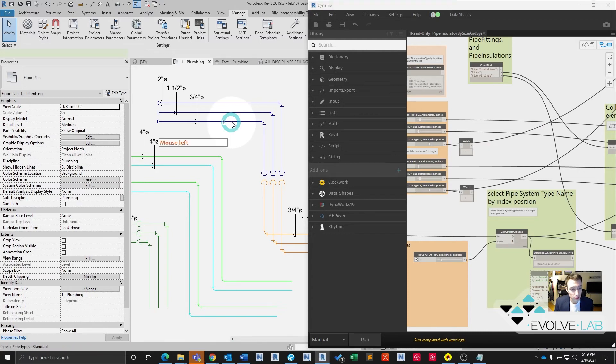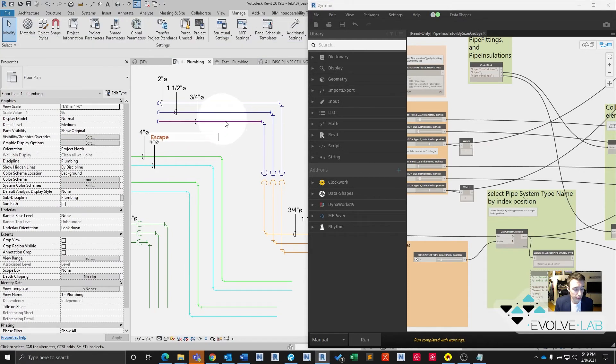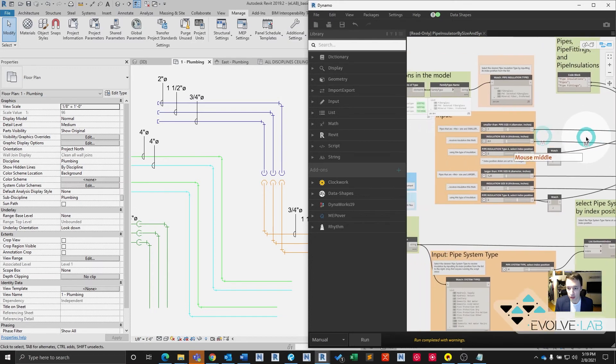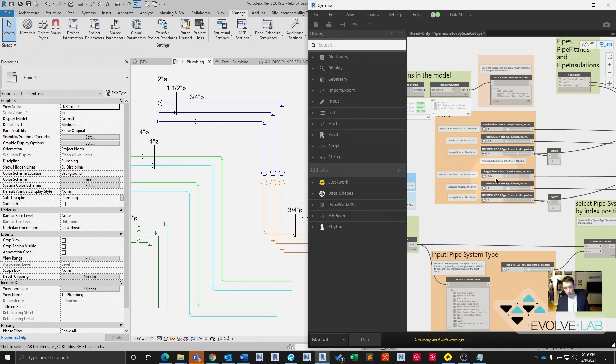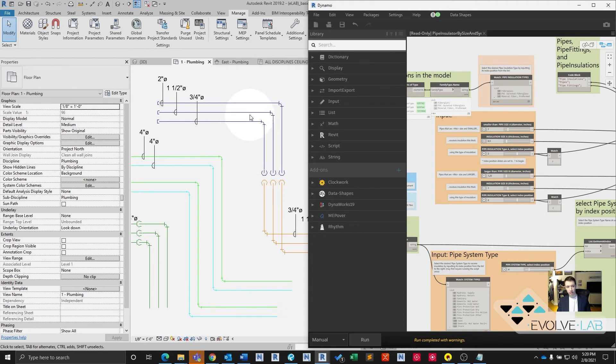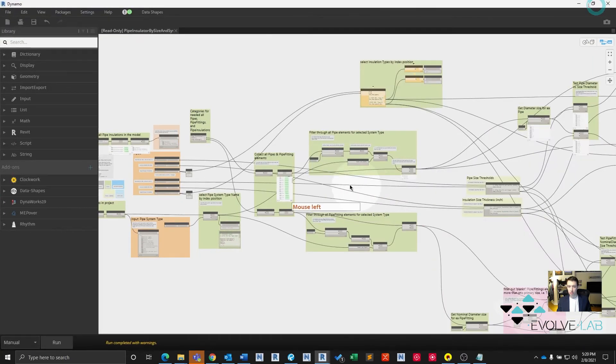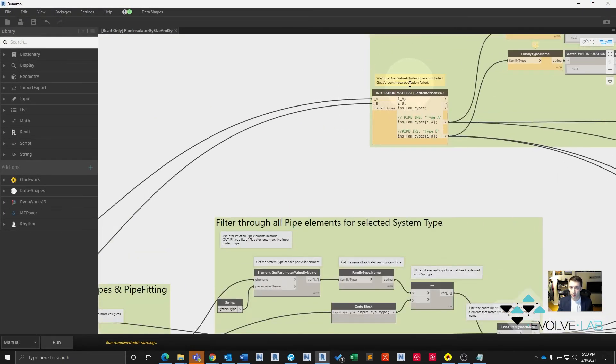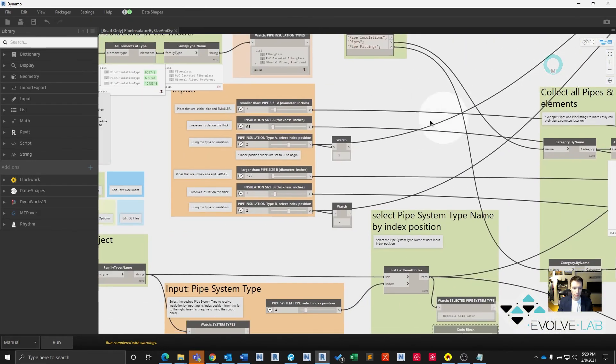Our three quarter inch domestic cold water, that's going to receive half inch insulation, right? Because it's less than one inch, so it's going to receive half inch insulation. However, our inch and a half domestic cold water, that's going to receive, because it's greater than an inch and a quarter, it's going to receive one inch insulation. Same with the two inch pipe here. So that's what we expect to see. Half inch insulation and inch insulation. Let's just make sure our script is running okay. And installation failed.